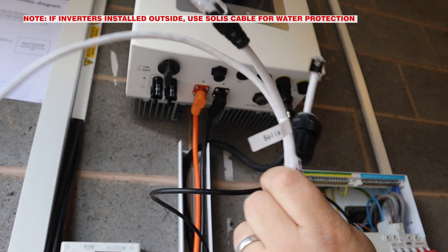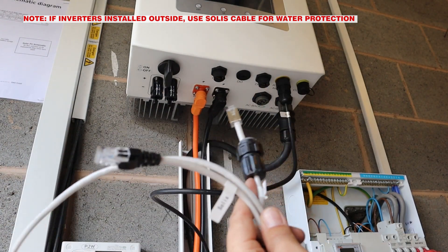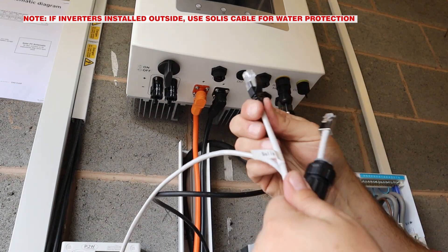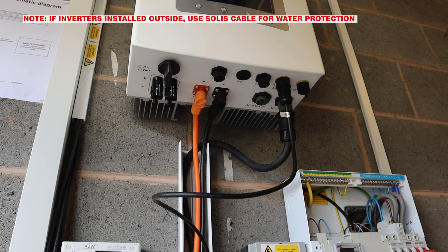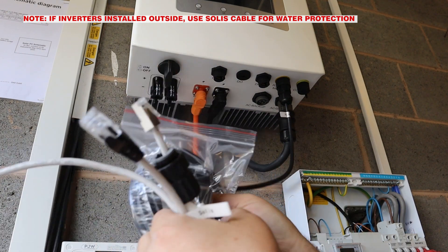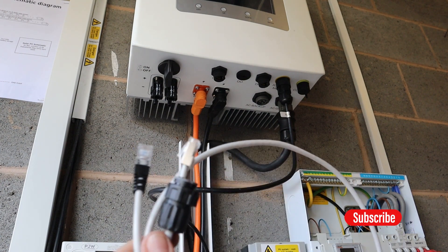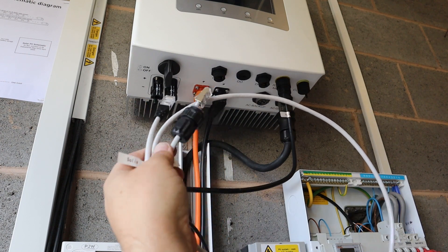Because we're fitting PureDrive batteries, I'd always fit the PureDrive kit. However, if the inverter's going outside, you need the waterproof end on the inverter, so you have to fit the Solis one. That's got the waterproof end on one end, labelled as inverter, and the other end is labelled battery but it's not waterproof. So just depending on which arrangement you've got — for us it's all inside — we're just going to fit this one this way around.